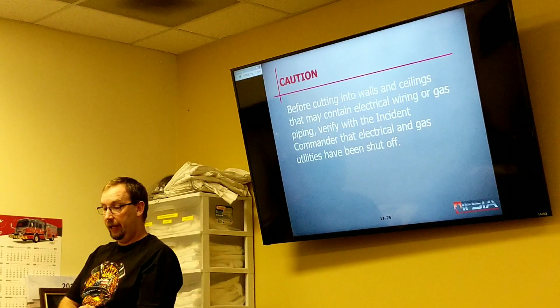Most of your commercial buildings will have 480 3-phase with a bunch of dry type transformers inside to knock them down. The book says it's required at a voltage in excess of 600, but I'd say 480 is more than sufficient. 600 and below is low voltage, 600 to 5,000 is medium voltage, anything over 5,000 is considered high voltage. Still, that'll just hurt you. You're gonna get a tingle, that's for sure.